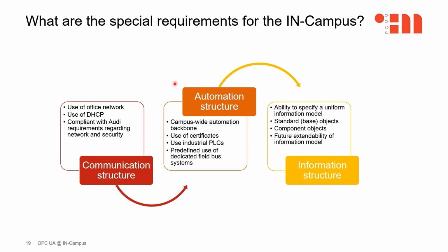Now a few words about the automation structure. Here too, there is a campus-wide standardized automation network to which all programmable controllers, the central and local operator stations, the central optimization system, and the programming stations are connected. The use of certificates to allow and deny connections must be made available. The operational devices and systems are monitored and controlled by the programmable controllers. Special local devices such as blinds, meters, lighting systems are connected to the programmable controllers via special field buses, which are particularly suitable for the respective applications.